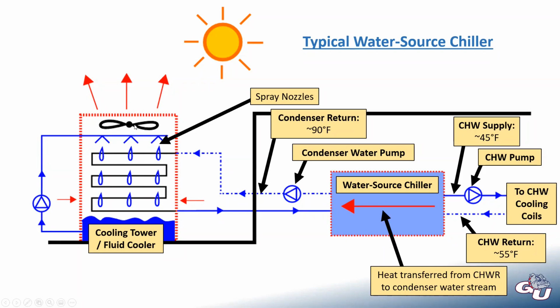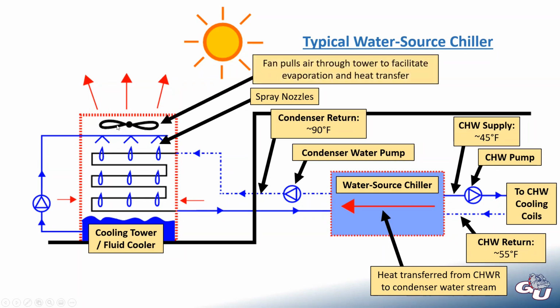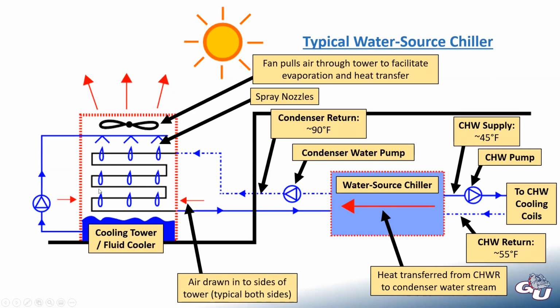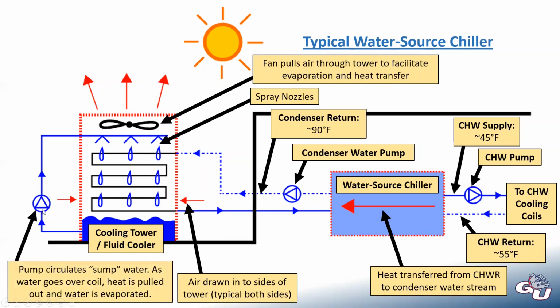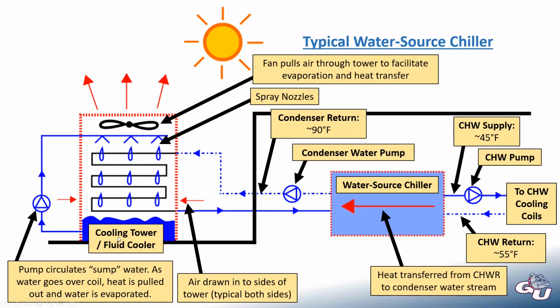And then we're also running this fan at the top. As we run this fan, this is pushing air out the top, or maybe the side, depending on how it's configured, which will pull in air through some openings in the side here. So as the fan runs, we're pulling air in through the side, which is also going to help with heat transfer. We have our pump here circulating the sump water. So this is pulling water out of the basin, pushing it through these spray nozzles, which mists over the coils, and ends up back in the basin. So that's kind of its own little mini loop on this side.